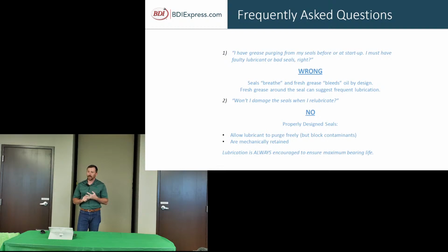So you might be having the right amount of grease, or you could be over lubricating if you are seeing a lot of grease. I was up on top of an office building, and this bearing was just covered in grease. It could have been over greased before they took over, but they're trying to get on a better maintenance practice and grease correctly. So that is actually wrong. So that is common.